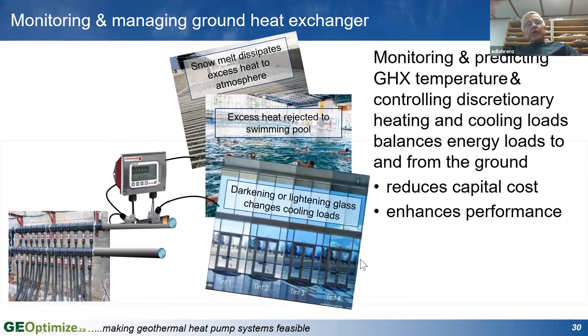Or there's working with Otter Tail Power on a project in Purim. By being able to change the tint of the glass on the building, we can change the heating loads and the cooling loads by about 25%. So in other words, instead of requiring 100 tons of cooling, we can reduce that to 75 tons, simply by inducing a small electric current into the glass that changes the amount of heat that's gained from the sun, and that changes how much heat we're trying to shove into the ground. That changes the amount of pipe that we need to service that load.